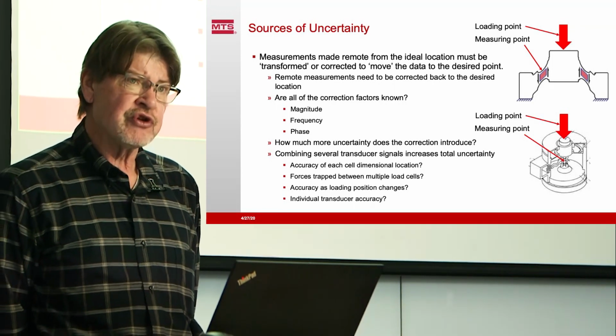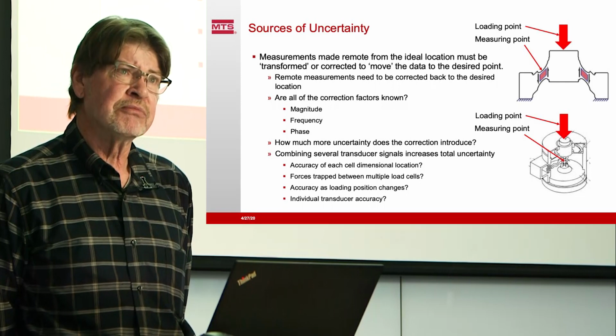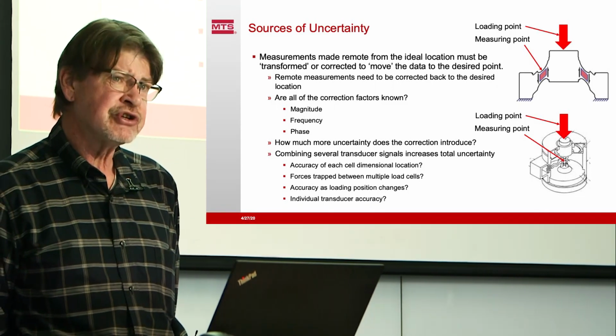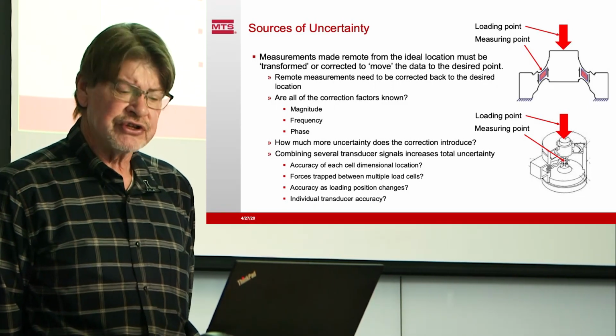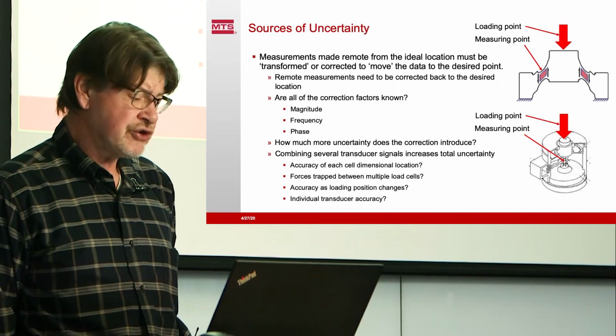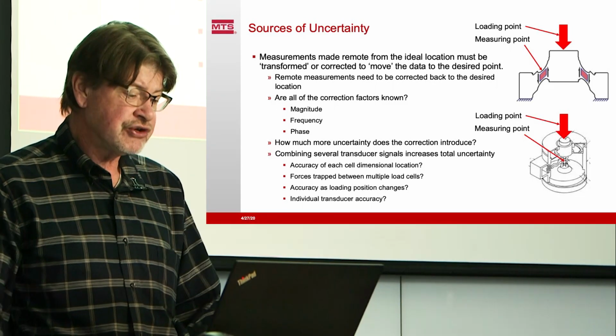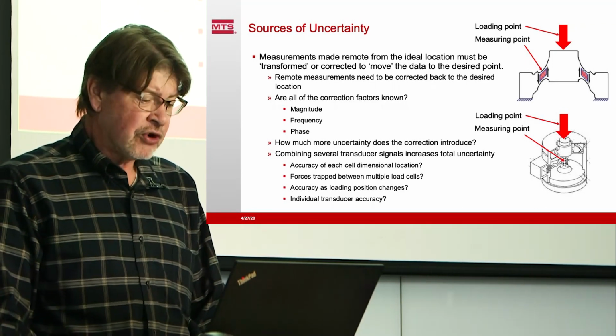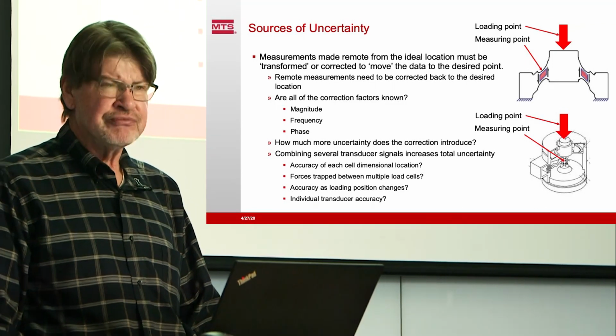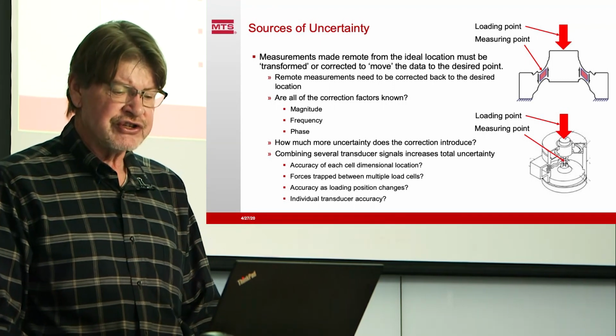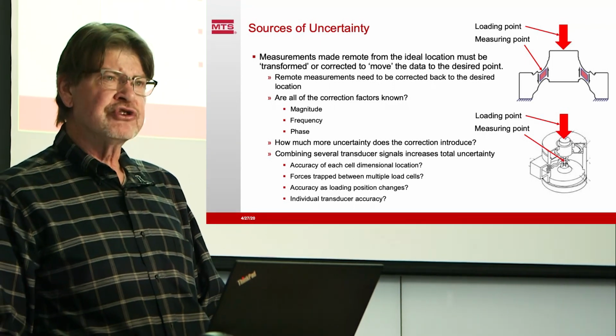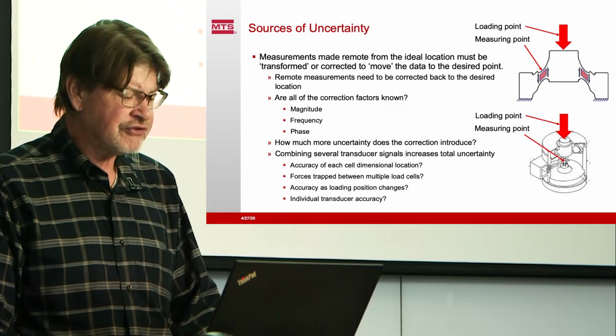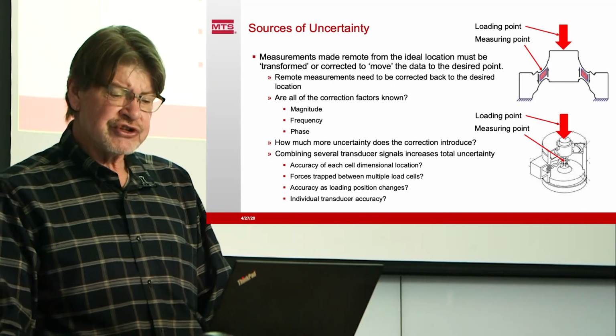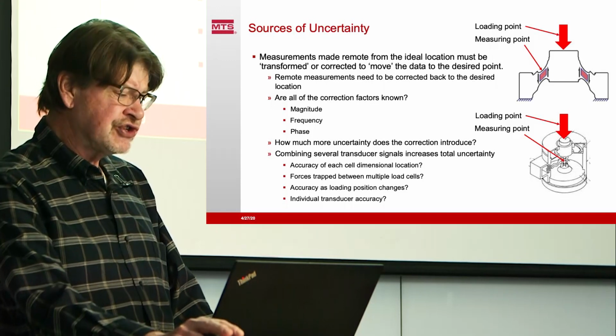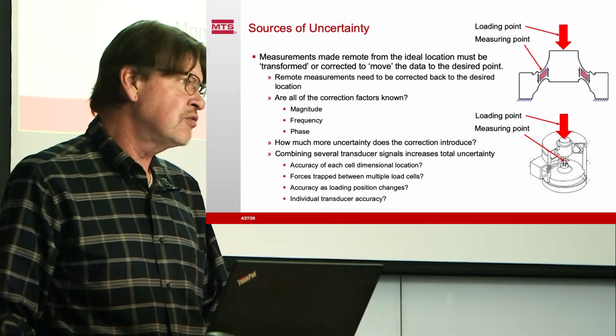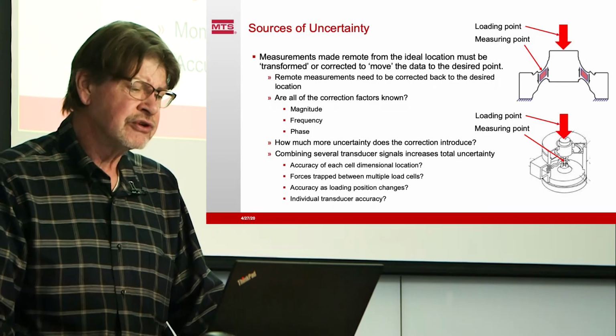Are there any forces trapped between four cells? For example, if they're bolted to a single plate and that plate changes temperature, how much force is trapped into the cells? We have no idea. We can't measure that. We can, but it is normally not measured and it's difficult to measure. Forces, accuracy as loading position changes. If we load right on the center of the load cell, we'll get one reading. What if we load 2 inches off the center? What about 10 inches off the center? What about the individual transducer accuracy? If we've got four transducers summed, we're going to multiply the errors of any one transducer, combining those signals.